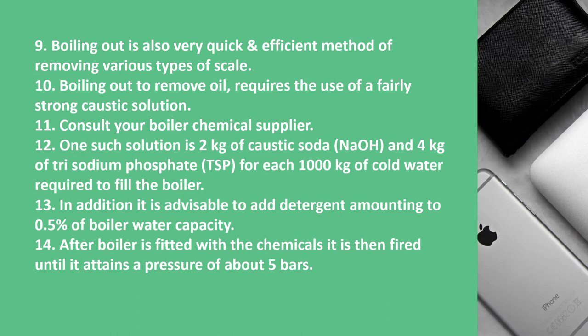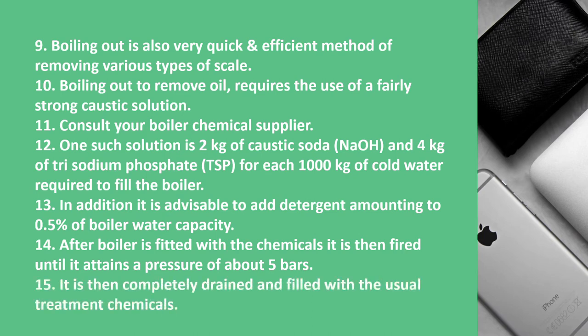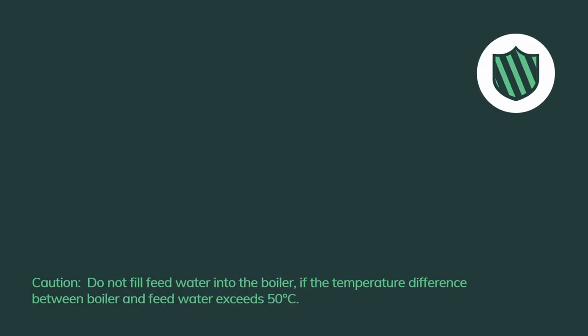After the boiler is filled with the chemical solution, it is then fired until it attains a pressure of above 5 bar, and kept at that pressure for approximately 5 hours. It is then completely drained and filled with the usual treatment chemicals. Do not fill feed water into the boiler if the temperature difference between the boiler and feed water exceeds 50 degrees Celsius.